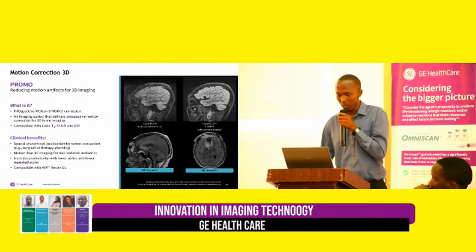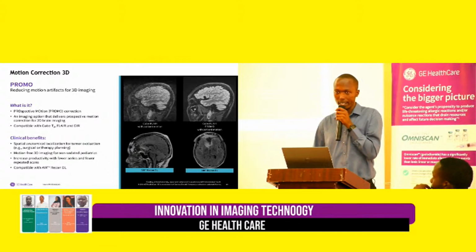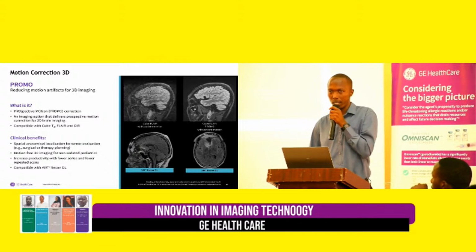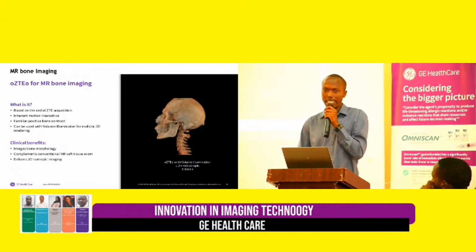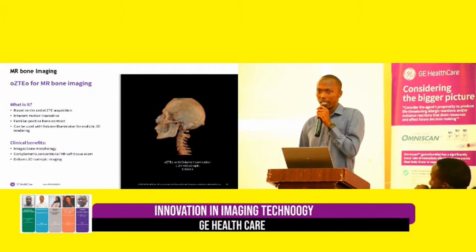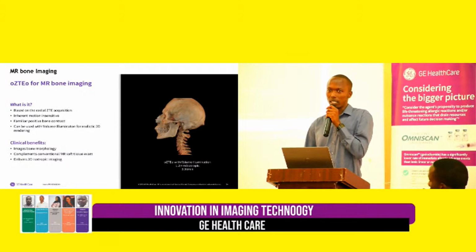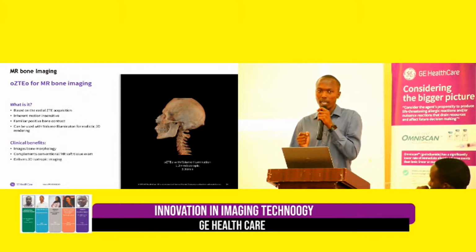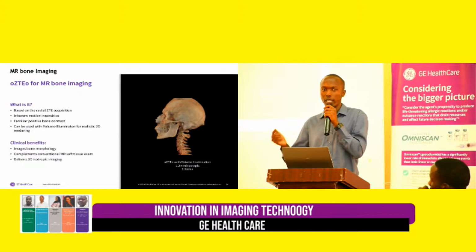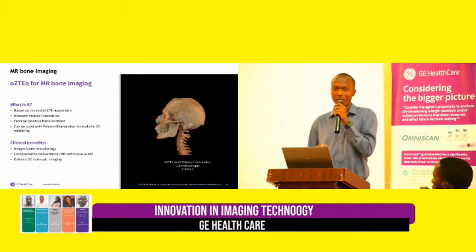Another is on bone imaging. Bone imaging, as I said earlier, was reserved for ionizing radiation mainly, so CT and X-ray, but now we can use zero TE imaging techniques. TE is time to echo, the time that you wait before you receive the signal after transmitting. Because of the very short T2 relaxation of bone, we are not able to get signal from bone routinely. But with the zero TE technique, that means there is no TE, we can get signal from bone.